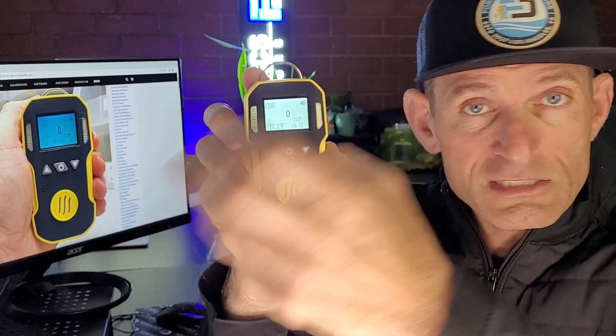The gas sensor that detects styrene is right over here and it presents you with the PPM concentration of styrene. OSHA has a recommended exposure limit for styrene at 100 PPM; NIOSH has it at 50 PPM. This gas detector covers that range — it detects from zero up to 100 PPM. You can set the alarm threshold where you like; you may want to set it at 20 PPM to be much more conservative and alarm much earlier to keep your people really safe. The alarms are adjustable — 100, 50, or 20 PPM — that is up to you.